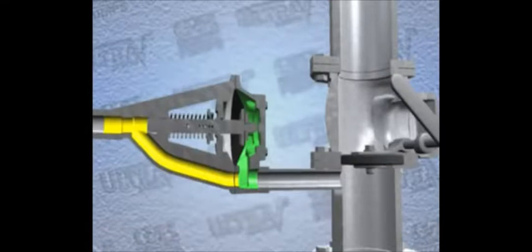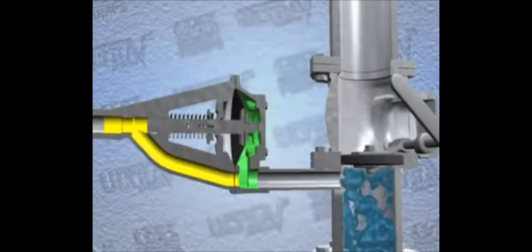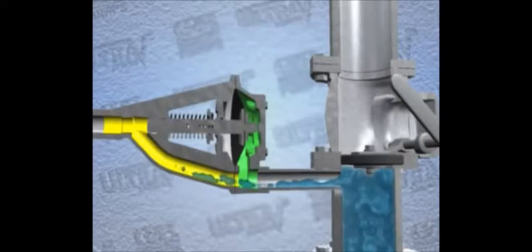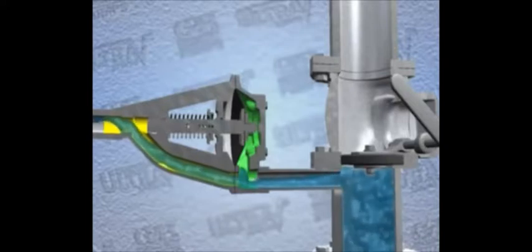An air release valve and discharge valve may be required if a pump is operating against substantial static discharge head. The air release valve is installed between the pump discharge outlet and a check valve in the discharge piping. During the priming or re-priming process, this valve allows any air in the pump and suction line to be vented and returned back to the sump.